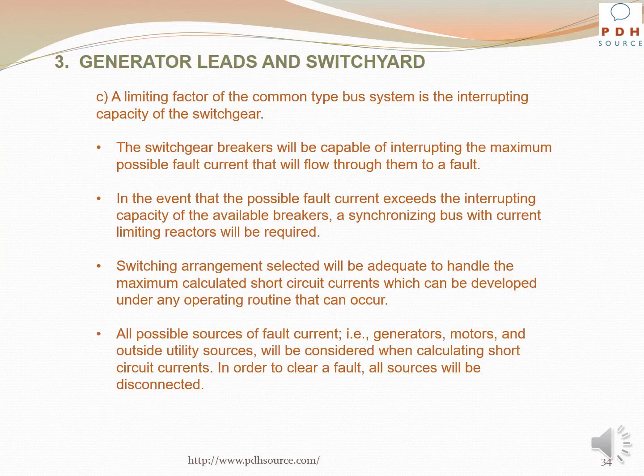Switching arrangements selected will be adequate to handle the maximum calculated short circuit currents which can be developed under any operating routine that can occur. All possible sources of fault current, that is, generators, motors, and outside utility sources, will be considered when calculating short circuit currents. In order to clear a fault, all sources will be disconnected.